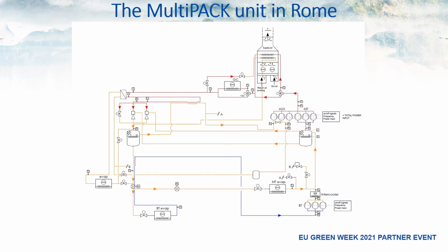It's a booster system, so we have medium temperature and low temperature compressor racks inside the same circuit. Of course, we have parallel compressors, here indicated as auxiliary compressors. We have the expansion via ejectors. Ejectors can remove the vapor from the receiver, which is located in the suction of the medium temperature compressors, but also recirculate the liquid if any liquid coming from medium temperature cabinets is present at the bottom of this receiver.